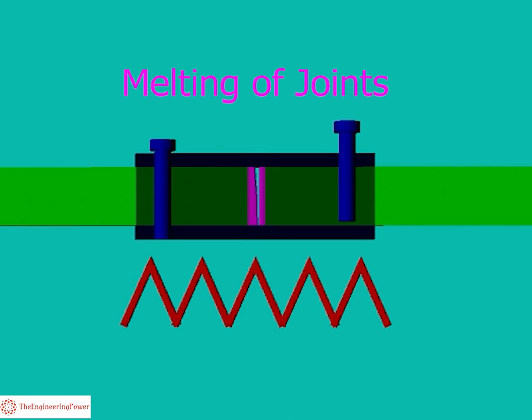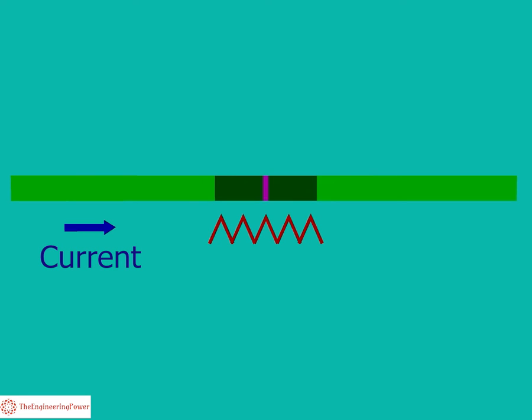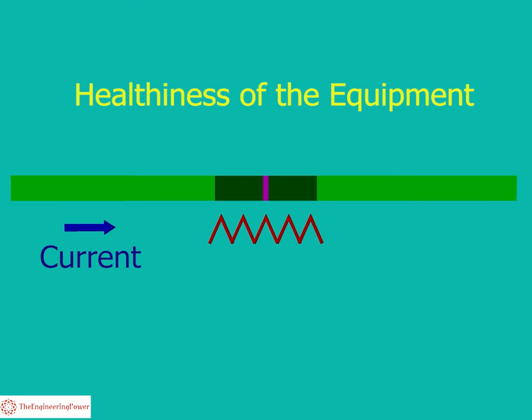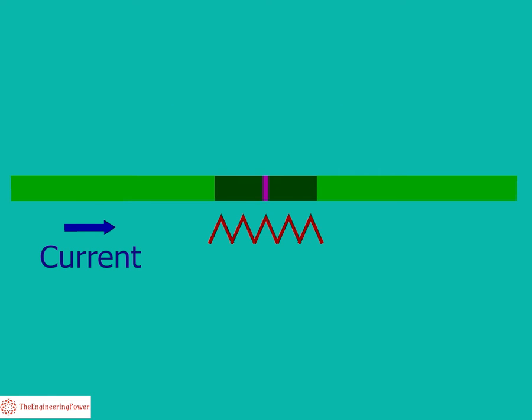It often causes a melting of the joints resulting in permanent fault. The contact resistance test needs to be carried out after a specific time to check the healthiness of the equipment like circuit breaker, bus bar joints, etc.